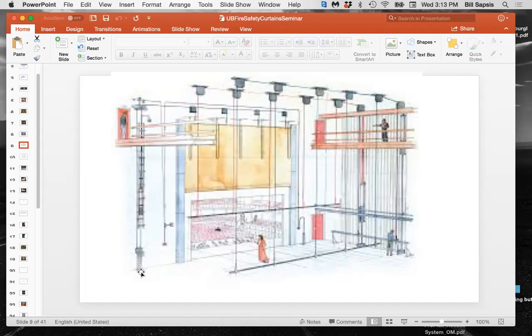So it's something you need to be aware of if your fire curtain does have that device, which will control the last 8 feet of descent. You need to make sure that it's functioning properly. And eventually, because they're temperamental and finicky, you will get fed up with it and you'll be looking to replace it with a winch of some device.